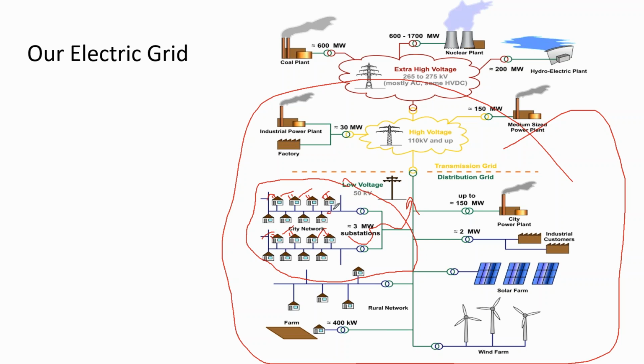The little transformers on the side of your house can go both directions, but at some point the utility distribution transformer starts to read 'uh-oh, power's going the wrong direction.' It sees it exactly the same as a power outage on the line. So when the utility says too much solar on a distribution circuit can cause their system to go haywire, that's absolutely true.